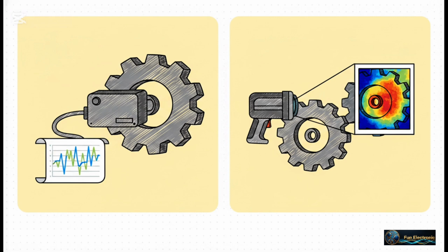A thermal imaging camera gives you a 2D surface map. It's a manual snapshot used during periodic walkthroughs to hunt down unknown hotspots. Fixed temperature sensors, however, are the steady, reliable watchdogs. They stay mounted to the machine 24/7, streaming continuous automated point measurements. They catch the gradual hidden thermal trends that a manual snapshot would totally miss.